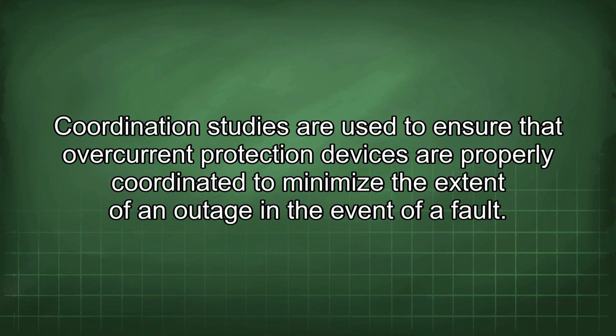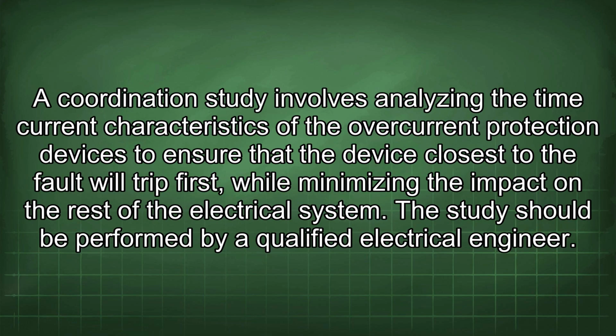operation. Coordination studies are used to ensure that overcurrent protection devices are properly coordinated to minimize the extent of an outage in the event of a fault. A coordination study involves analyzing the time current characteristics of the overcurrent protection devices to ensure that the device closest to the fault will trip first, while minimizing the impact on the rest of the electrical system. This study should be performed by a qualified electrical engineer.